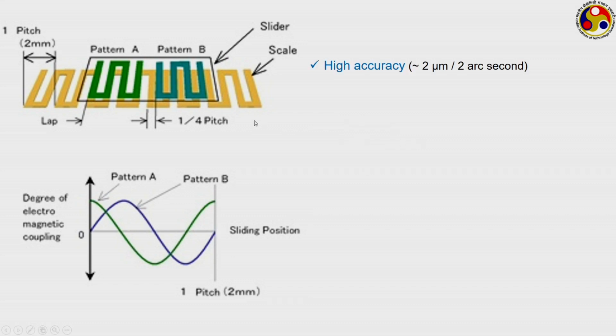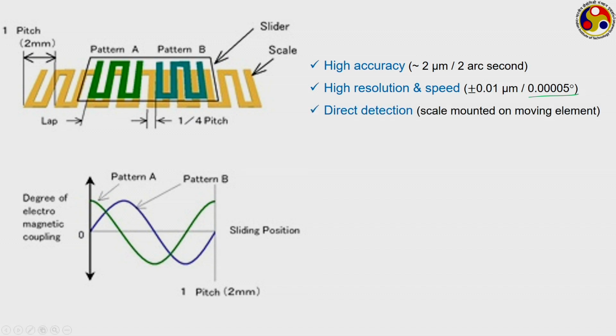Inductosyns give quite high accuracy, at the level of just 1 or 2 microns, or for rotary displacement, as small as 2 arc seconds. We get very high resolution at the level of plus minus 0.01 micron, and also very high speed. For rotary scale resolution, we are talking about 10 to the power minus 5 degrees - extremely small resolution. There is direct detection, with a scale mounted on the moving element, so we directly get the value of the displacement.